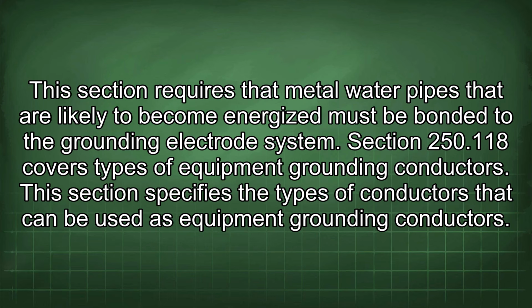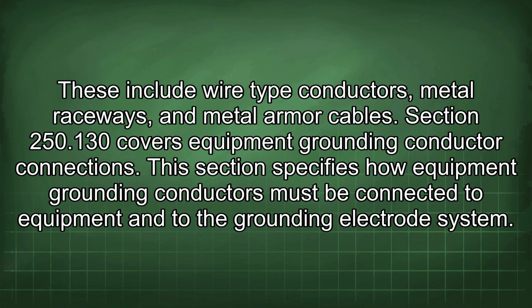Section 250.118 covers types of equipment grounding conductors. This section specifies the types of conductors that can be used as equipment grounding conductors. These include wire-type conductors, metal raceways, and metal armor cables. Section 250.130 covers equipment grounding conductor connections. This section specifies how equipment grounding conductors must be connected to equipment and to the grounding electrode system.